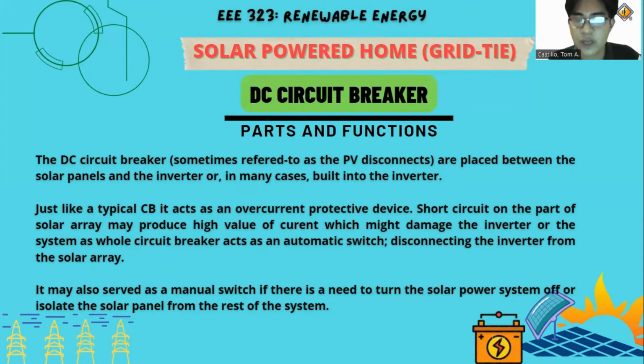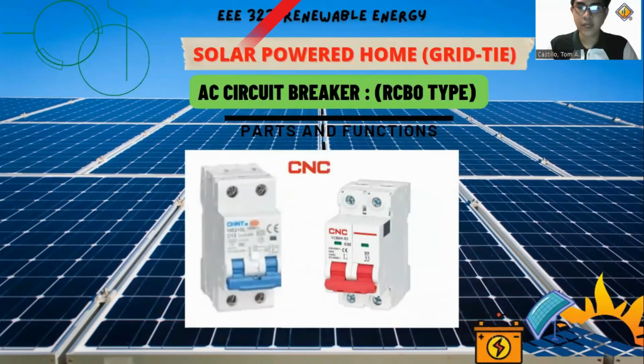So the DC circuit breaker acts as an overcurrent protective device. For example, the appliance can only tolerate 20 amperes, and then 40 amperes of current suddenly comes in. The function of the breaker is to trip so that the 40 amperes cannot enter the appliance before it damages the electronic device it is protecting. So, it will trip. Next is the AC circuit breaker, the RCBO type. So, this is what we will use.